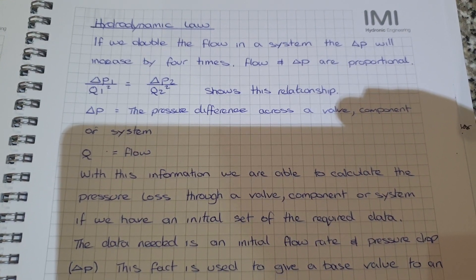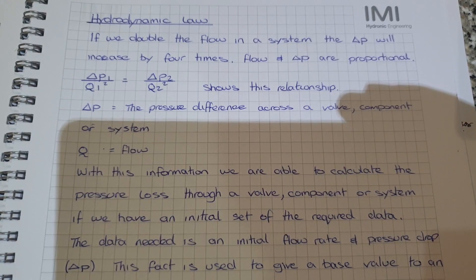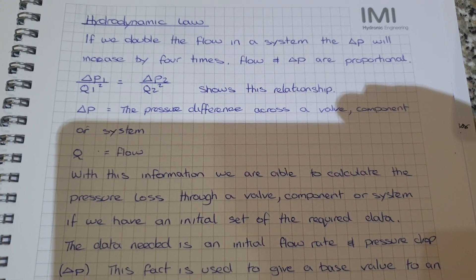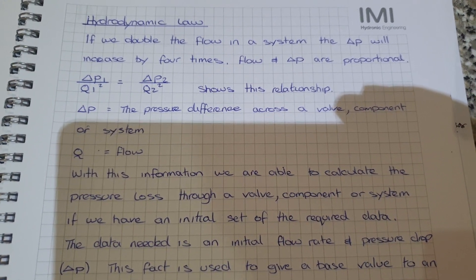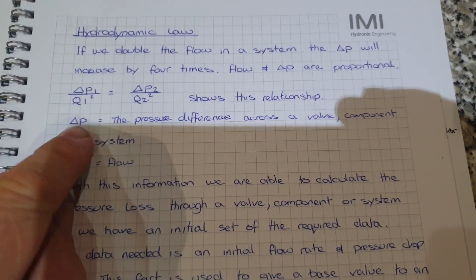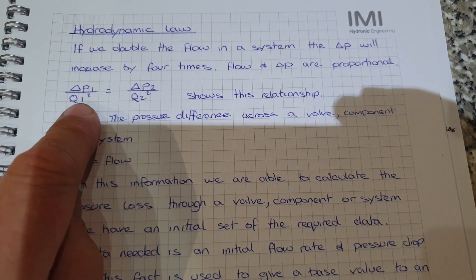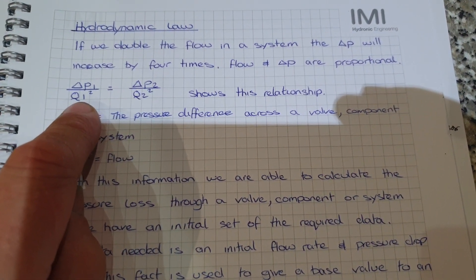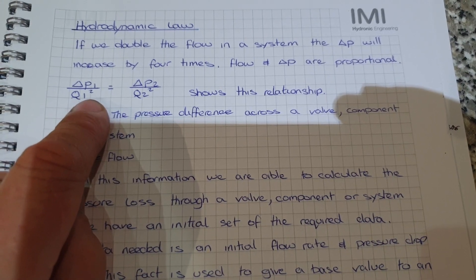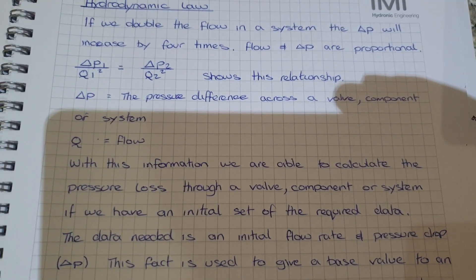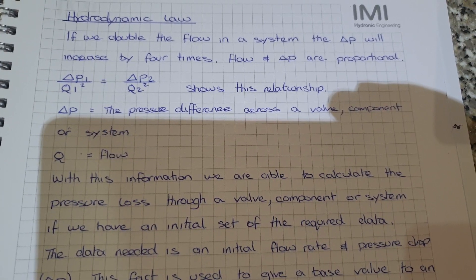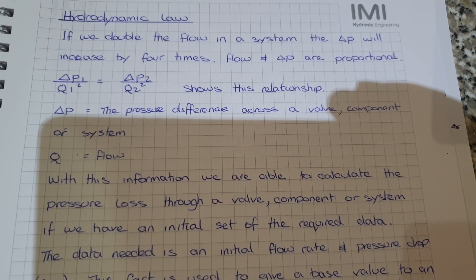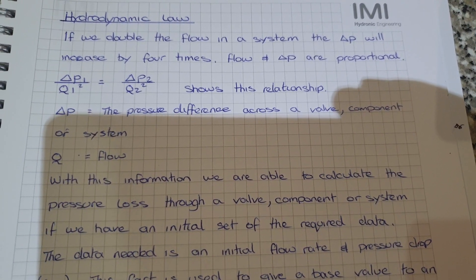So, hydrodynamic law: if we double the flow in a system, the delta P will increase by four times. Flow and delta P are proportional. The relationship is shown by the following formula: delta P1 divided by Q1 squared equals delta P2 divided by Q2 squared.